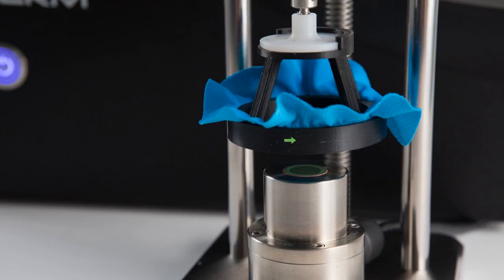There are some different accessories available with the system. This is an embroidery hoop that's attached to the compression test accessory and just allows for a different way of presenting the sample to the sensor. We'll get into some of these sampling dynamics as we go through the presentation, but the green area of the sensor that you see pictured here is the active area of the sensor. The fabric is brought into intimate contact with that green sensor chip, and that's where the measurement occurs. We'll be going through the dynamics of the measurement and the principles of operation here in a few seconds.